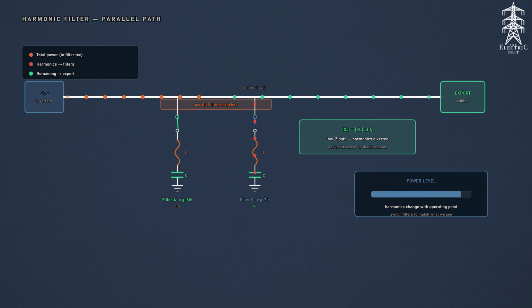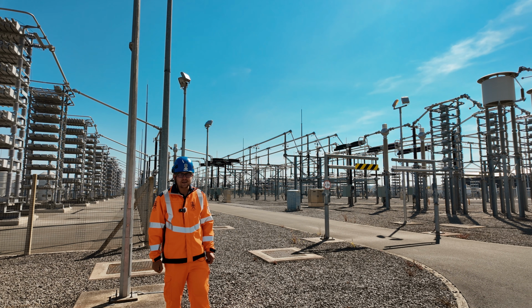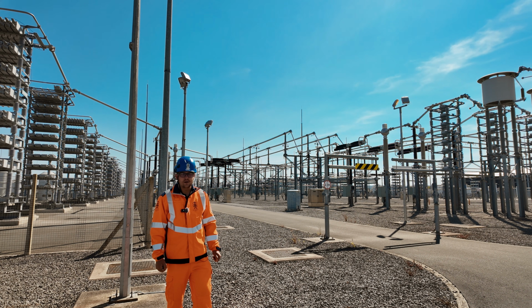At the harmonic frequency, this branch presents a very low impedance. At 50 Hz, it behaves predominantly like a capacitor, so it doesn't short our fundamental frequency power to earth. Instead, it supplies useful capacitive reactive power to the AC system.